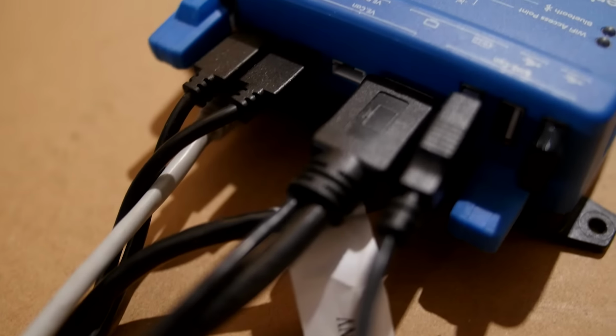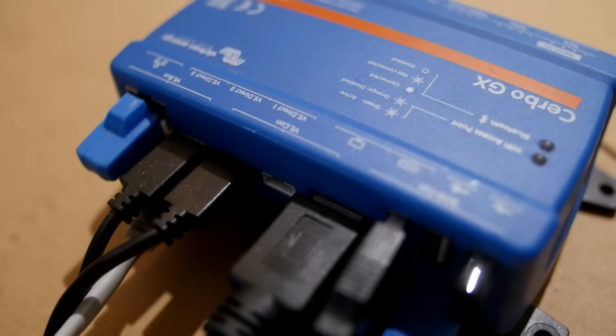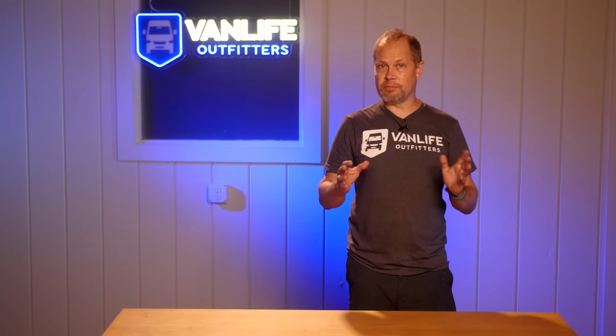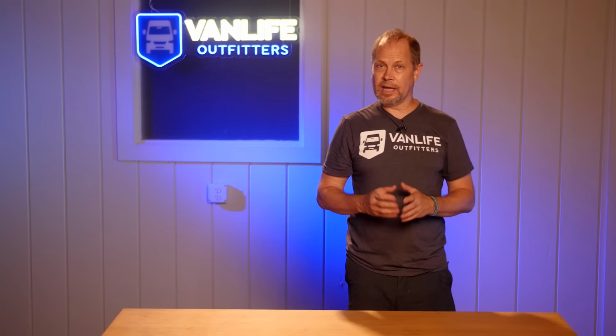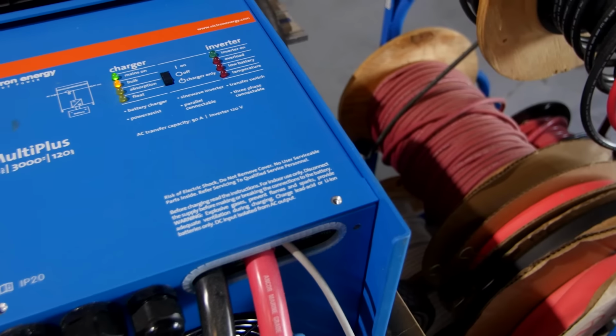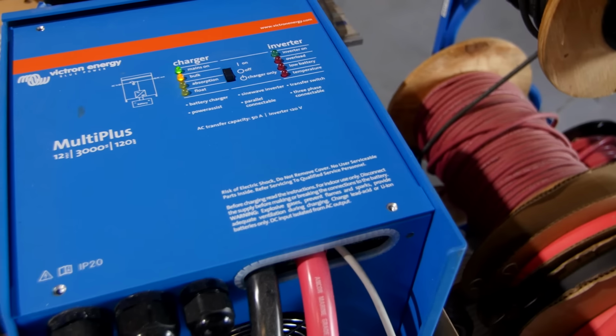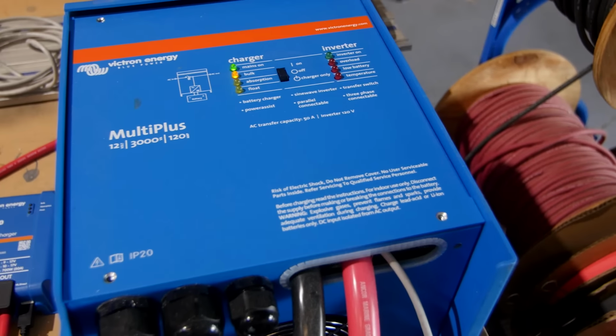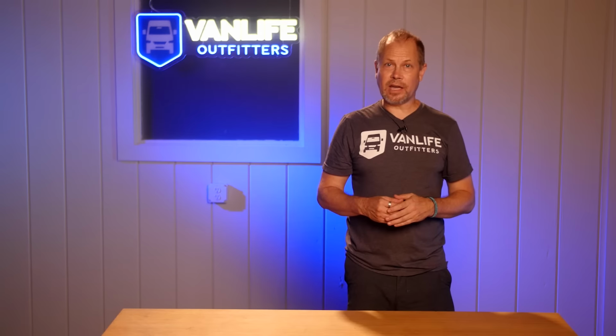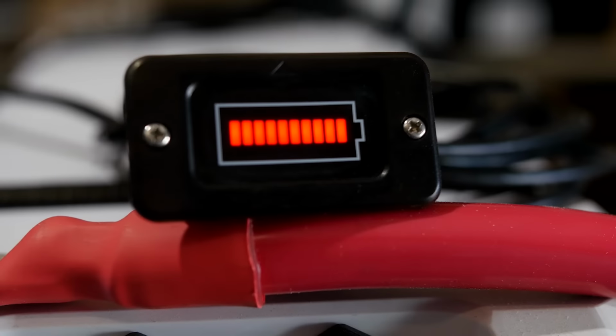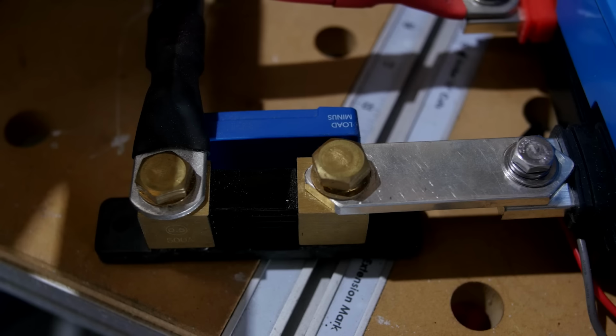The Orion XS is communicating with the Cerbo GX through its VE.Direct connection. This is one of the many new awesome features of the XS Orions. We also have a MultiPlus 12/3000/120 inverter charger that's communicating with the Cerbo GX over VE.Bus. In this test system, we actually have two battery monitoring shunts. There's one that's built into the ePIC battery, and we also have a Victron SmartShunt here for testing and comparison. You normally wouldn't do this, we're just nerding out for the sake of our testing.